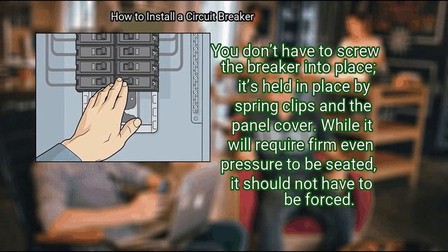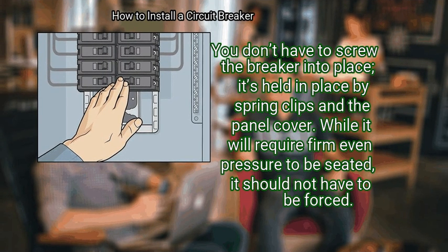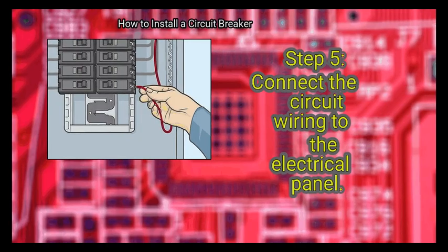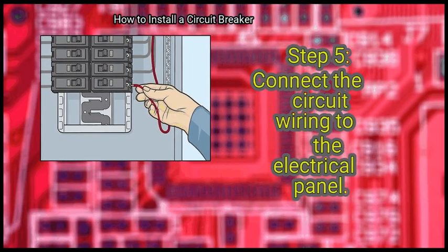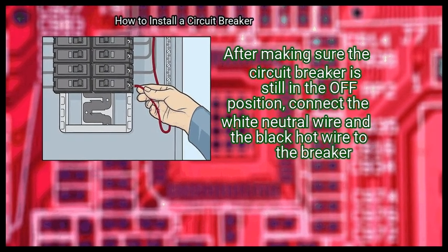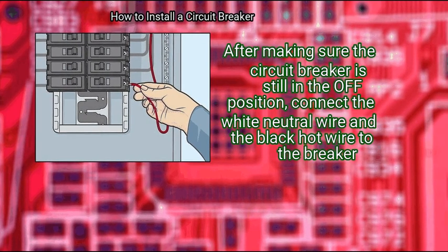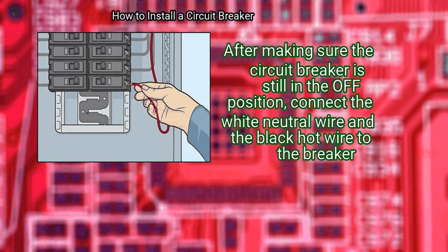It's held in place by spring clips and the panel cover. While it will require firm even pressure to be seated, it should not have to be forced. Finally, connect the circuit wiring to the electrical panel. After making sure the circuit breaker is still in the off position, connect the white neutral wire and the black hot wire to the breaker.